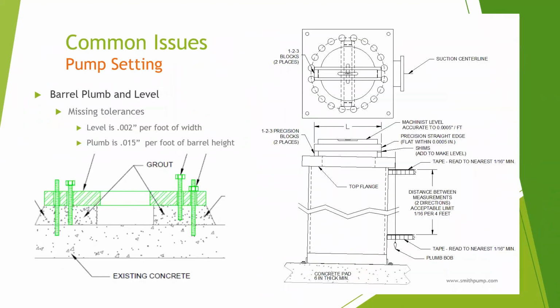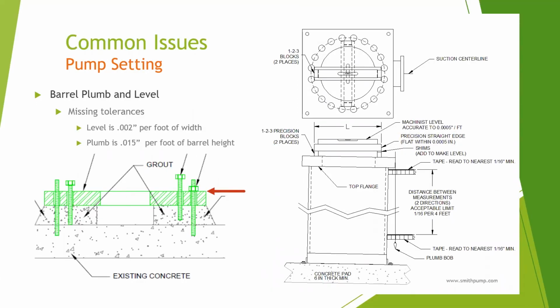The levelness of equipment is also crucial to bearing life, vibration, and overall equipment life. We want to see the sole plate or barrel top levelness specified as 0.002 of an inch per foot or less. Barrel plumb should have a maximum lean of about 1/16 of an inch per 4 feet, which works out to 15 thousandths of an inch per foot of height.